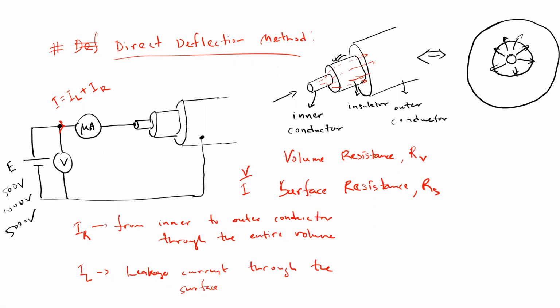However, if we want to eliminate the effect of the leakage current, we have to create a bypassing path so that the current IL doesn't pass through the ammeter. It is bypassed before passing through the ammeter. For that reason, a wire can be used which is connected with the surface of the insulating material. This sort of connection using a wire is called a guard wire.